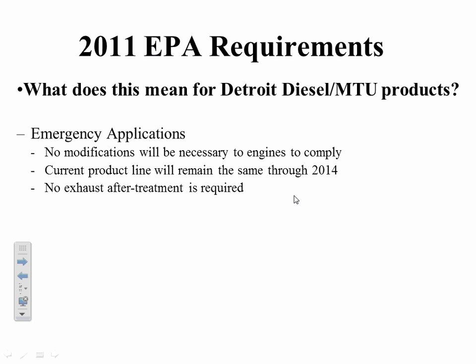It's not just emergency lights or emergency elevators or emergency fire pumps. This is coming out of the air quality group of the EPA. Bear that in mind. So this generator set for that data center, if the power fails, that's an emergency generator set. You run the whole data center on it. Correct. By this definition, if the power has failed, it's emergency. It's not bad.